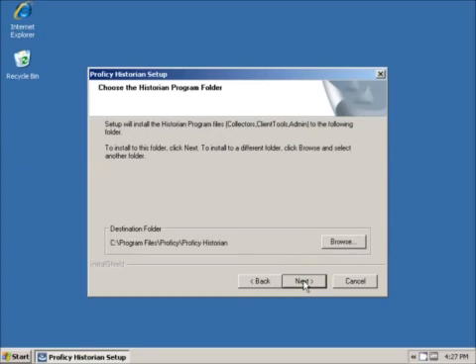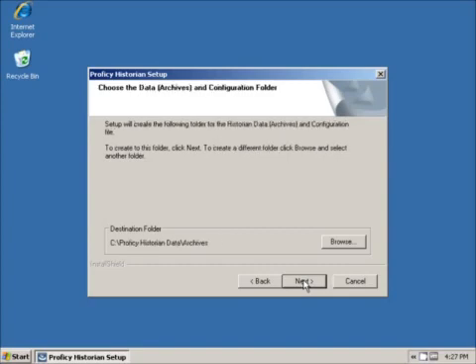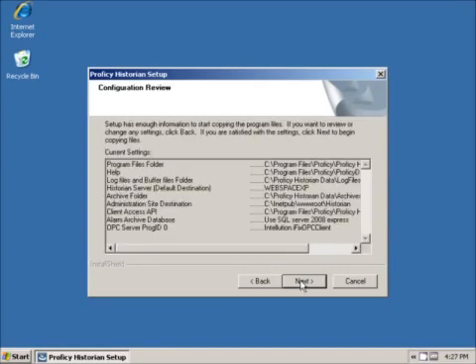Next we review the installation folder for the executables and support files. Note that the next dialog is to specify the location of the data archives. Here we configure the path for the Historian data archives. If you have a D or other drive for the files, you can easily browse to and select a different location. Mapped drives are not recommended for the Historian archives. This dialog is a review of the installation configuration. Review the settings and go back if you need to make any changes. Click Next to proceed with the installation.